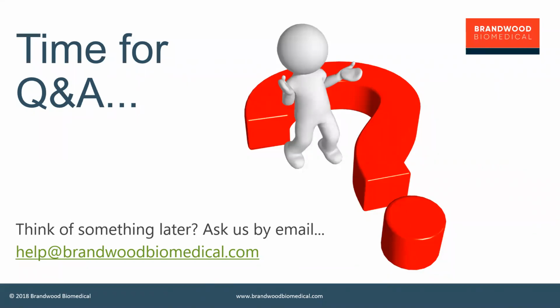And then, because this is a risk management process, you can go through risk control and you might be able to change something about the device which would decrease the probability of that endpoint actually occurring. So if you fail a biological test, if I can put it as crudely as that, which is frankly the way everyone still thinks about this, then you don't just retest it. You perform risk control. You do some change, and then you can evaluate, will that change actually improve the outcome for that endpoint? And it may not be necessary to actually test it again.